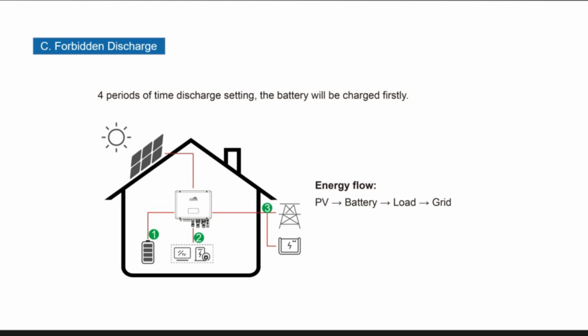Forbidden discharge: after setting the period of time, during this period the battery will not discharge. For the energy flow, PV energy will charge the battery firstly, and go to the load and then to the grid.